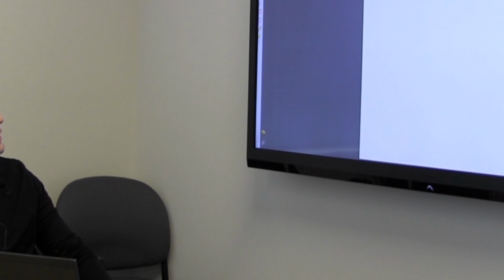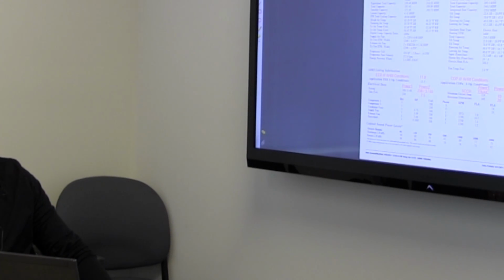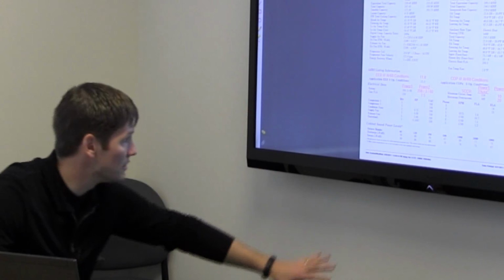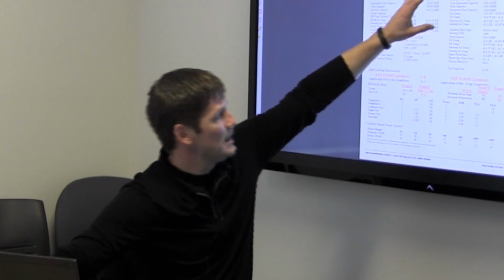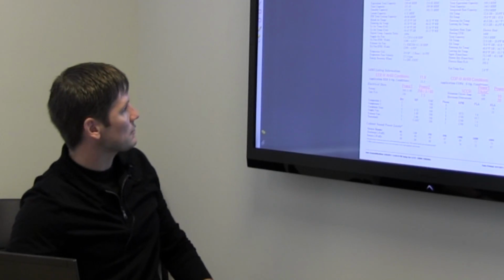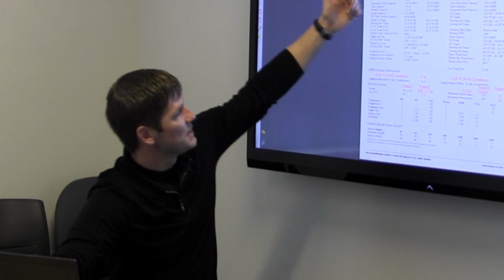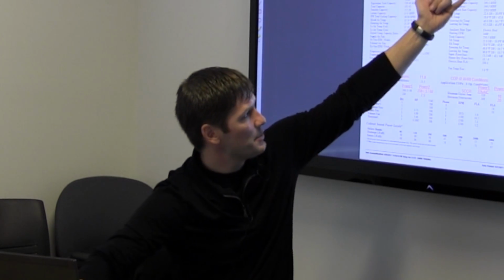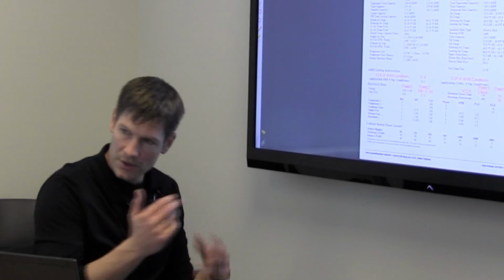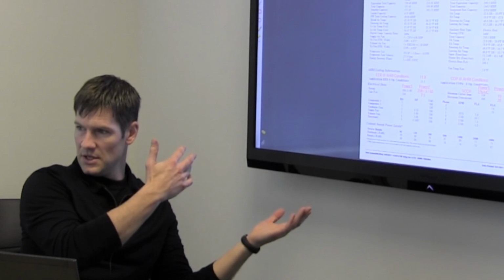So we've seen most of this, so we'll blow through it. Again, now we just have even more performance information. We've got cooling, we've got heat pump heating, and we have electric heat. Here's your pressure drops if you were wanting to see, say, the heat wheel. The heat wheel pressure drop is 0.82 inches when it's clean and new. If you were to take that pressure drop in 5 years and see that it's 1.5 inches, you'd probably know, okay, now I need to clean that.